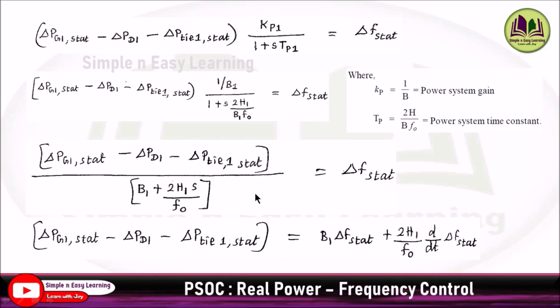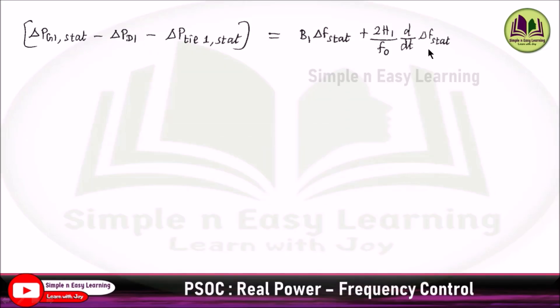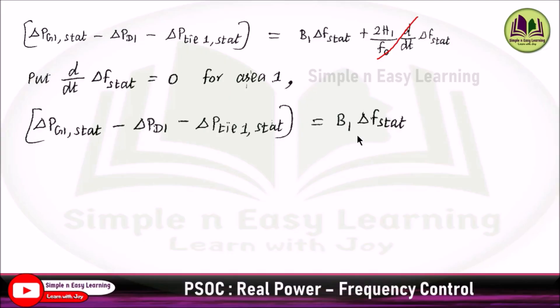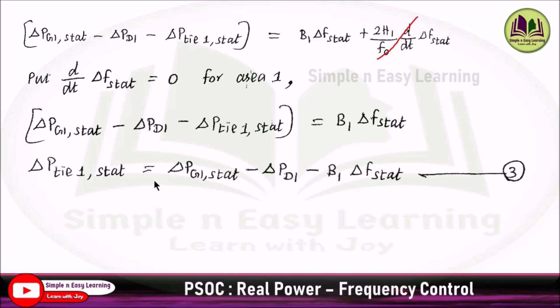Taking the whole term to the other side multiplied by Δf_stat: the first term is B1·Δf_stat and the second is (2H1·s/f0)·Δf_stat. Replacing s with d/dt, for steady-state analysis, d/dt of Δf_stat = 0, so the second term vanishes. The remaining expression allows us to find ΔPti1_stat, giving equation 3: ΔPti1_stat = ΔPg1_stat − ΔPd1 − B1·Δf_stat.